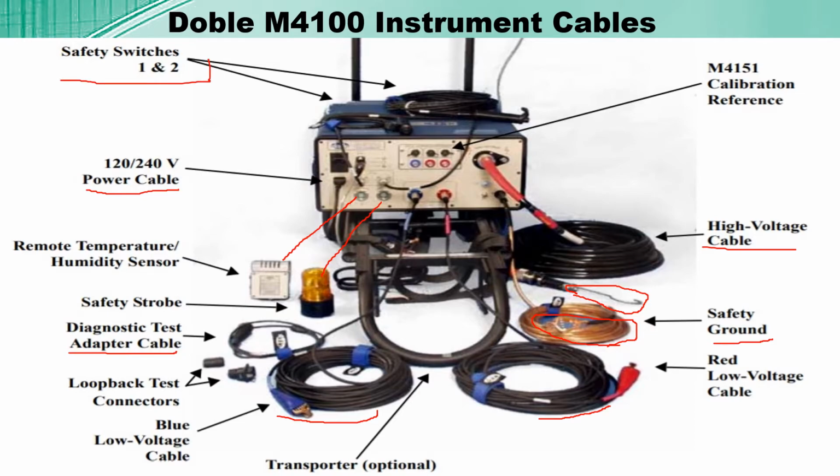What does the safety switch actually do? When you give the command to run the test and press OK, the test will not run unless you press these two safety switches. Yes, both the switches should be pressed. Only then will this kit give the inserted kV to my CT and the test will run.